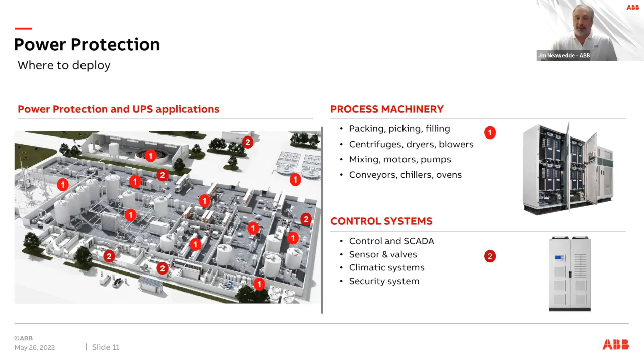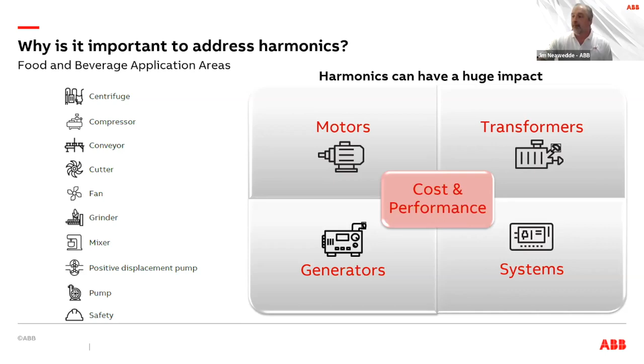One of the issues we run into with power systems is harmonics. Harmonics come about from nonlinear loads, and they can affect your motors, transformers, and generators in your systems. I've shown the areas where harmonics can directly impact. What is a harmonic? Basically, when you have a regenerative load or a nonlinear load, typically like this 6-pulse drive, you can see that there's a ripple that's been put onto the power grid. And so the idea here is we want to make sure that we clean up that power.